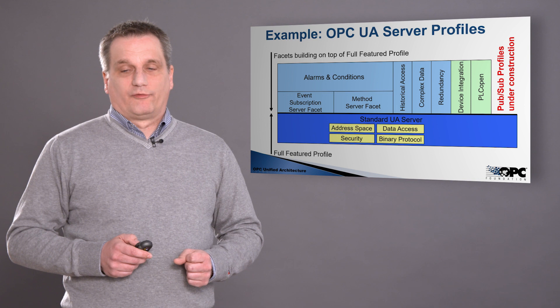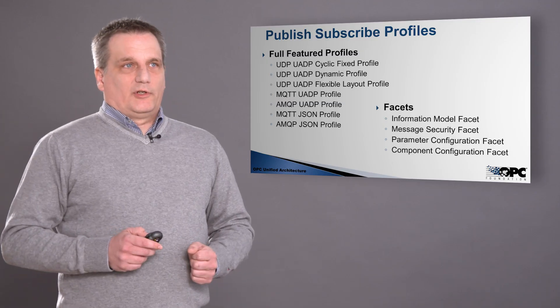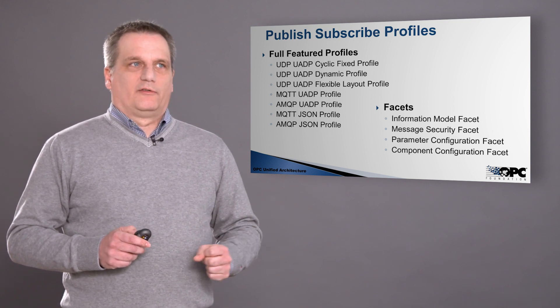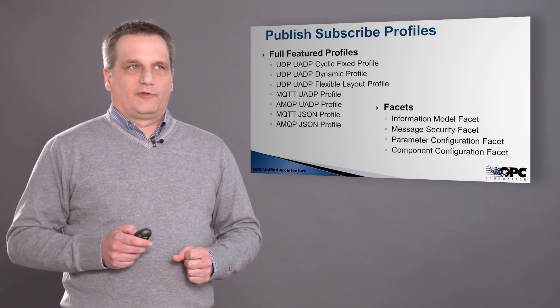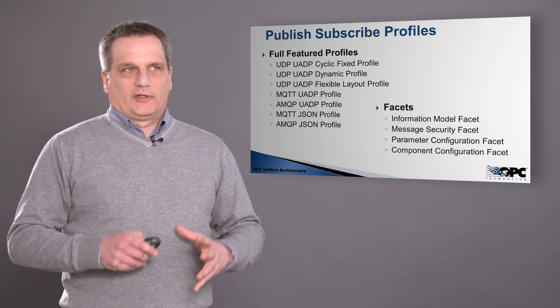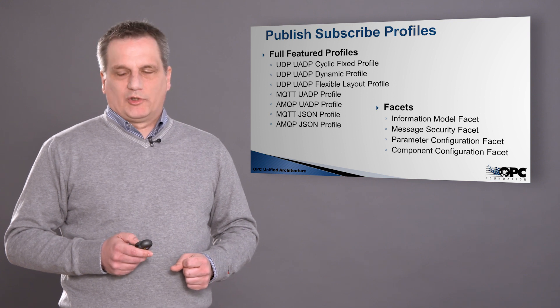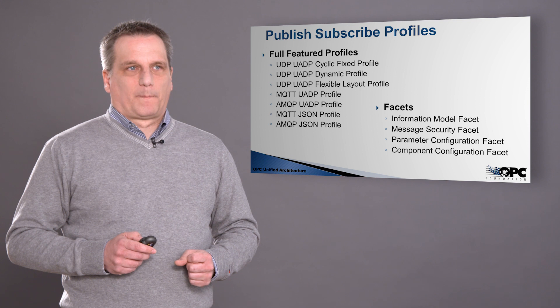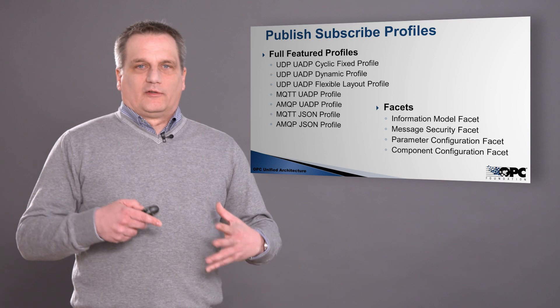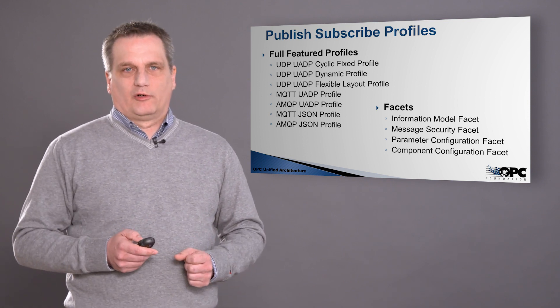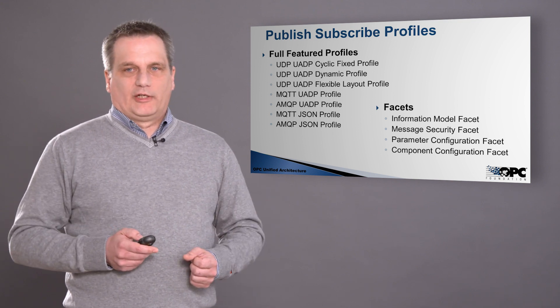There will be profiles for the pub/sub communication as well. We have a list of published/subscribed profiles. There are full featured profiles that describe the encoding and the transport — for the cyclic fixed profile, the dynamic profile, and the flexible layout profile that describes how the messages are put together and sent. We also have profiles for communication over MQTT, AMQP, and even a JSON encoding profile. In addition, the information model facet describes the pub/sub configuration that resides inside the information model of the server, and we have parameter configuration facets and component configuration so you can configure the pub/sub messages through the information model of the OPC server.